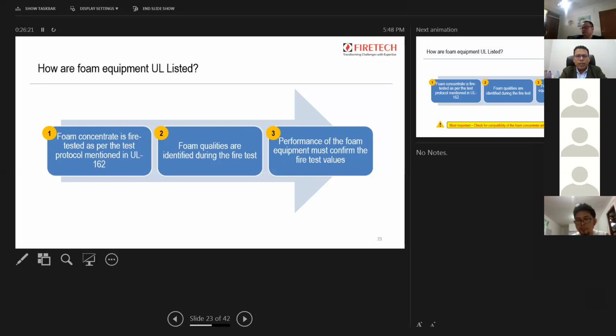So here it consists of basically three steps. First, the foam concentrate is fire tested as per the test protocol mentioned in UL 162. Now after the foam concentrate is fire tested, the foam qualities are measured during the fire test, that is the foam expansion and drainage. And the third step is the performance of the foam equipment must conform to the fire test value. So the foam equipment manufacturer has to ensure that whatever foam is produced by his equipment has the same qualities as those obtained during the fire test. So this is a three-step approach followed in UL for the UL certification of foam suppression systems.